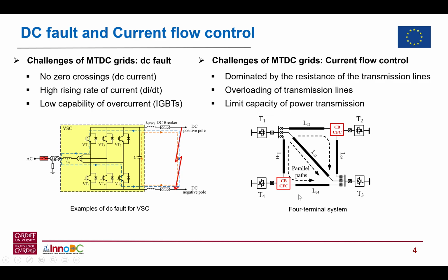But there are still a lot of challenges on the way to building MTDC networks. The first one is DC fault. Since there are no zero crossings of DC fault currents, it is more difficult to interrupt DC fault current. Another reason is that the DC fault current increases very fast, which means that the protection system needs to isolate the fault in a very short time.